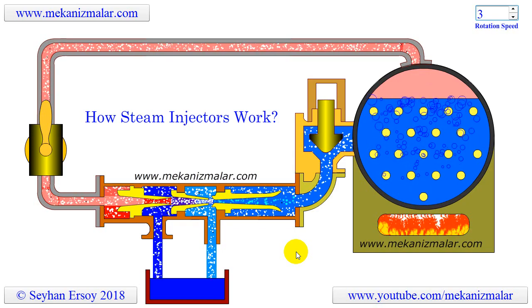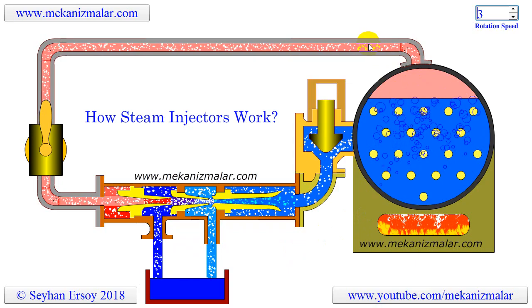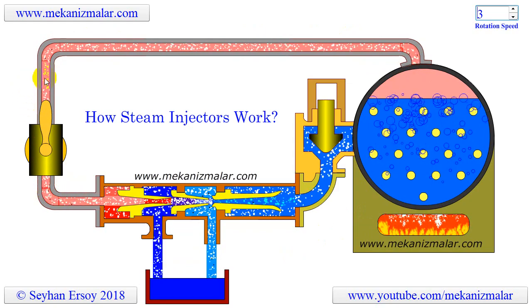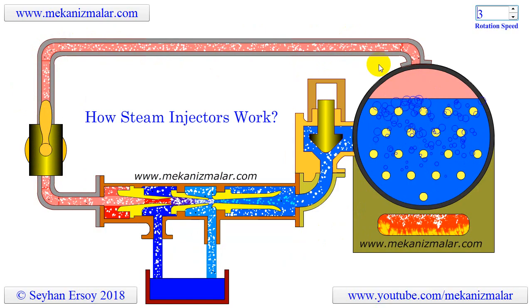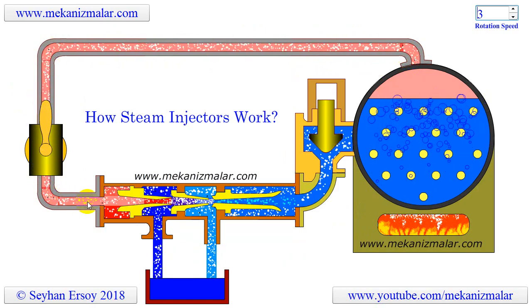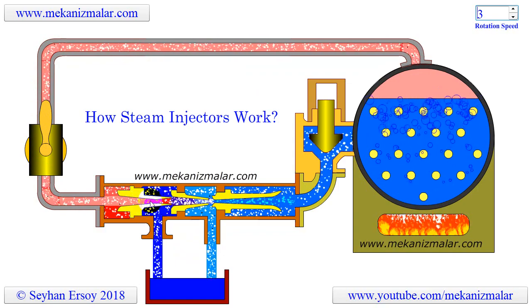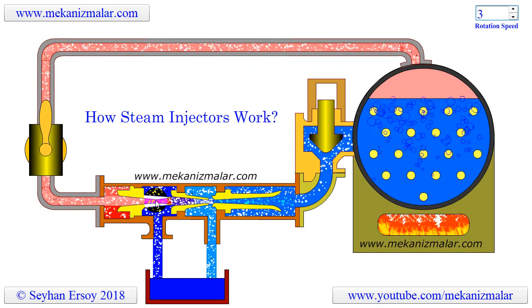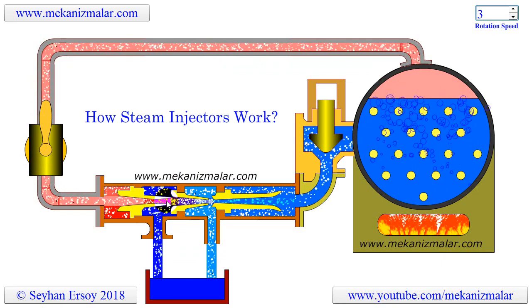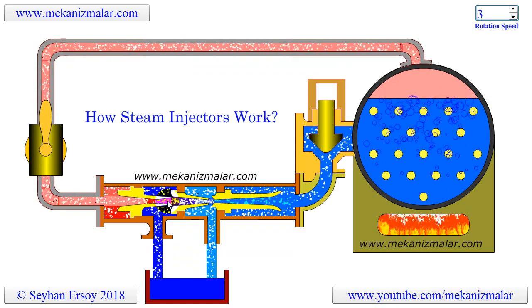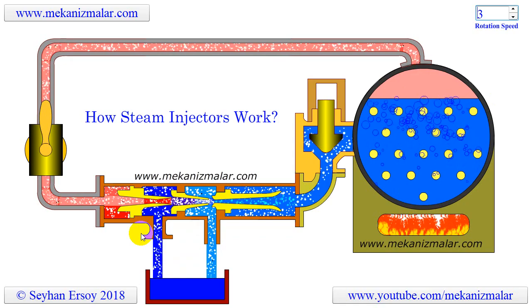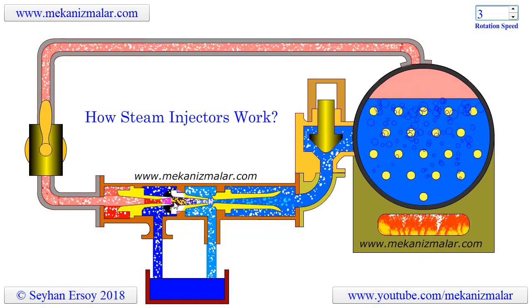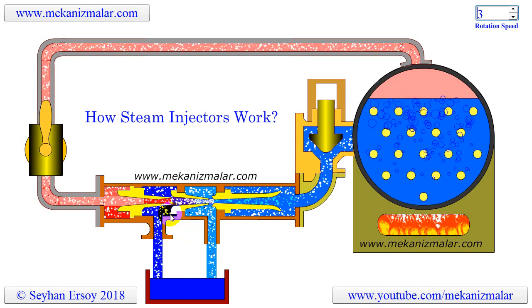Here is how a steam injector works. Steam taken from the boiler is sent to the injector with high pressure and low velocity. This flow is indicated by the red background with white dots showing the direction of flow. The flow is then directed to the converging-diverging steam cone. In the cone's converging section, the steam velocity is increased to the speed of sound. At the diverging section, the pressure is further reduced and converted to kinetic energy, where steam moves faster than the speed of sound. By the time steam leaves the cone, its speed is much faster than the speed of sound, but its pressure is below atmospheric pressure. The flow is shown here with a light red background.